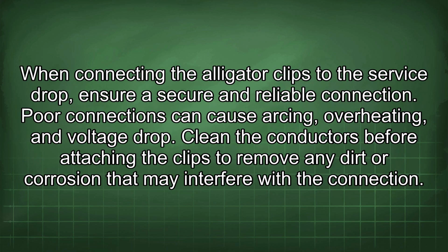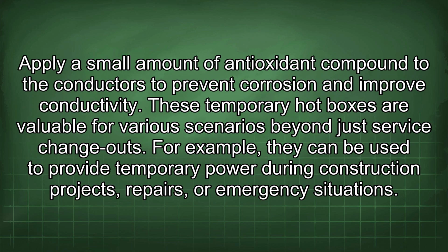When connecting the alligator clips to the service drop, ensure a secure and reliable connection. Poor connections can cause arcing, overheating, and voltage drop. Clean the conductors before attaching the clips to remove any dirt or corrosion that may interfere with the connection. Apply a small amount of antioxidant compound to the conductors to prevent corrosion and improve conductivity.